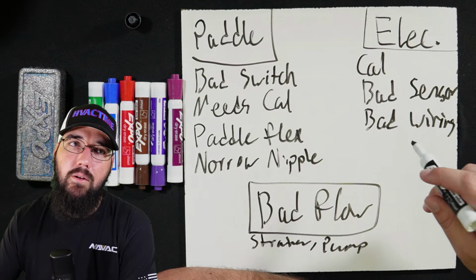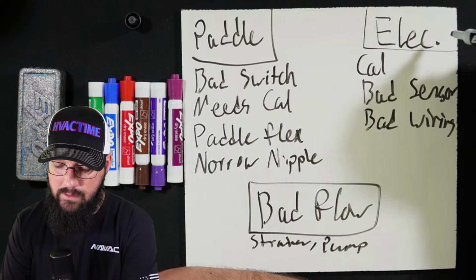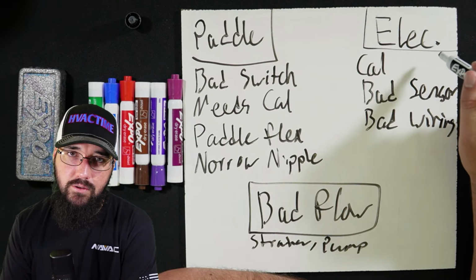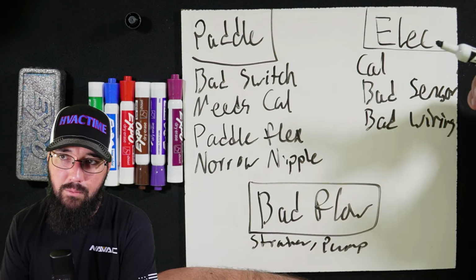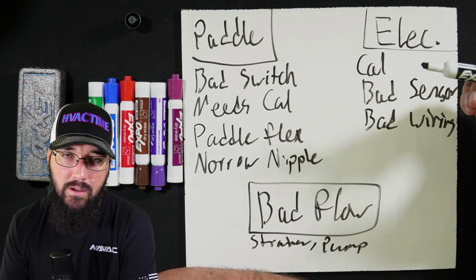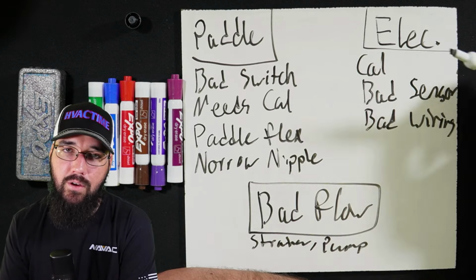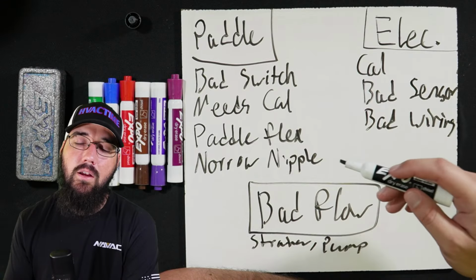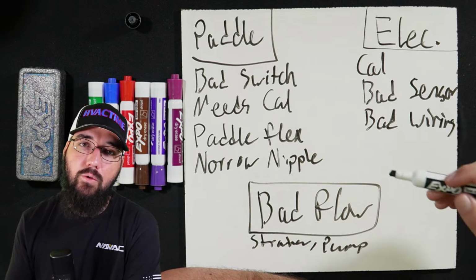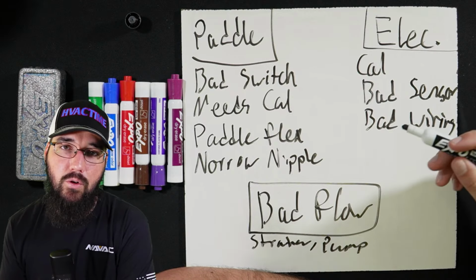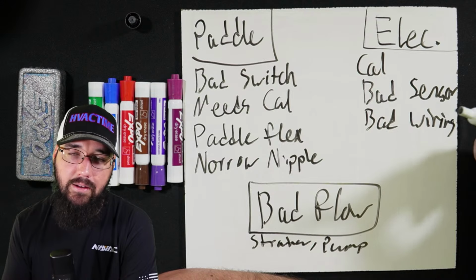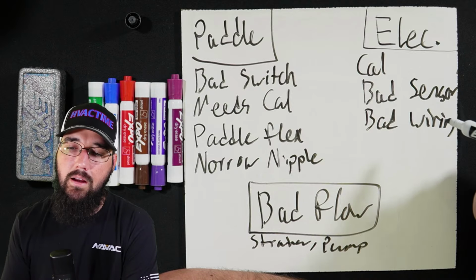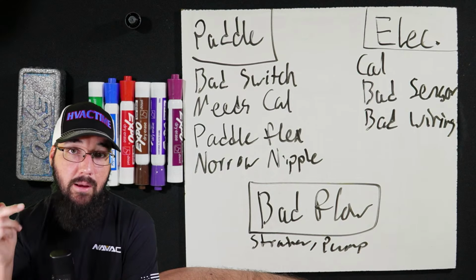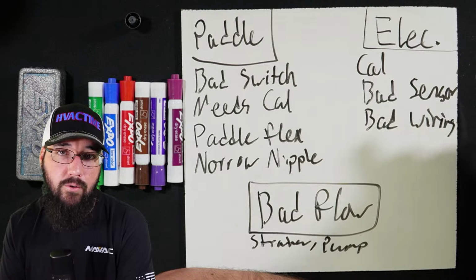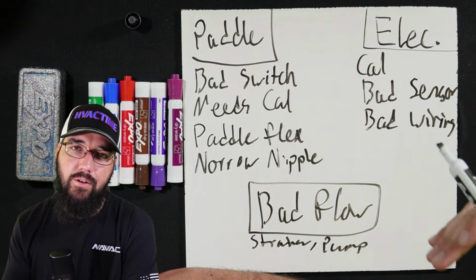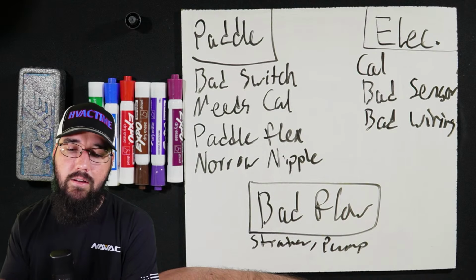And a DP sensor, so if you're measuring differential pressure for this, that could be calibration on the transducers. That could be a set point issue. Maybe the set point isn't configured correctly on the DP sensor control. Or the pressure taps where the transducers go on could plug up all the time, which is one of the reasons I hate DP sensors: the pressure taps just get full of crap. Even on a closed loop chill water loop, they get full of crap, and the transducer no longer reads accurately, and it just causes all kinds of chaos.